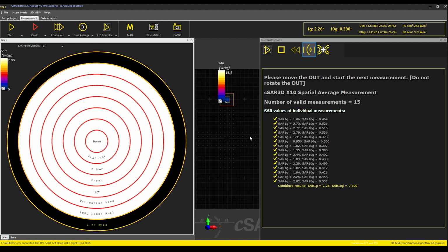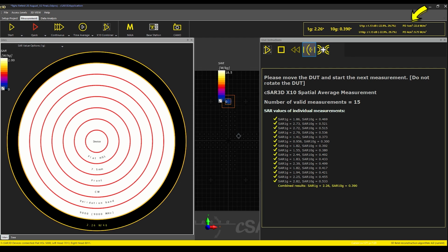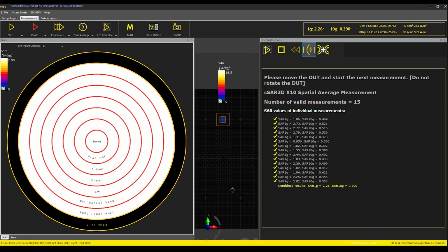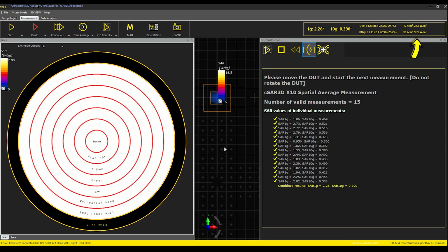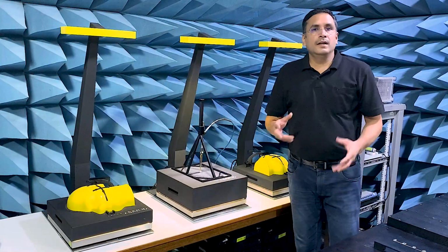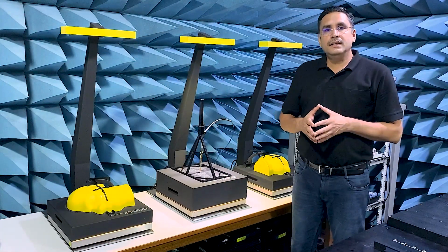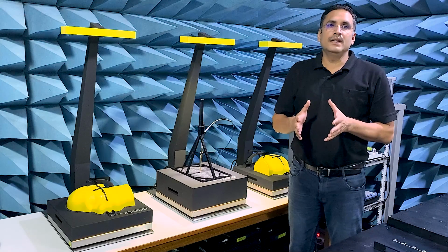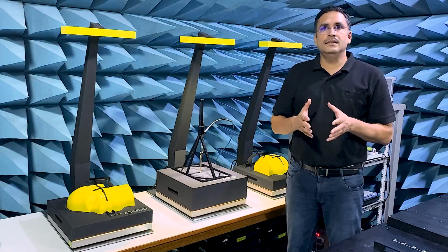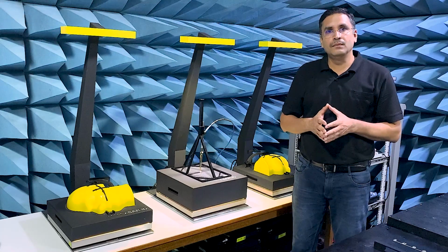The values for epithelial power density are also calculated and are shown here. They are 22.6 watt per meter square for 1 centimeter square averaging and 9.75 watt per meter square for 4 centimeter square averaging area. Therefore, I extended the test to the entire set of validation sources as defined in Annexure D of IEC 62209-3.